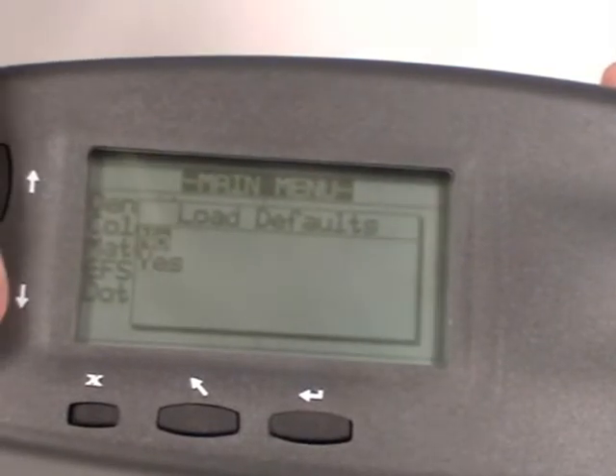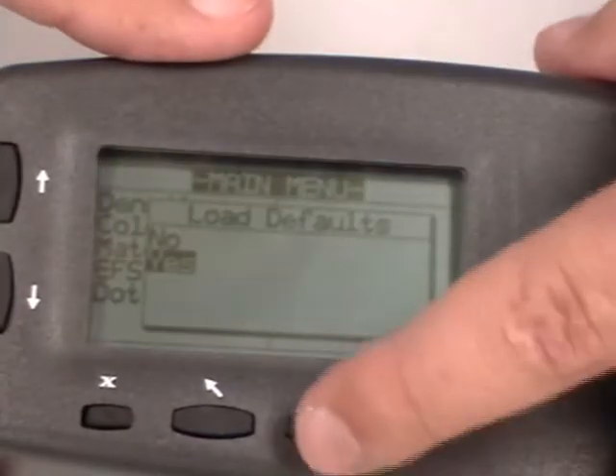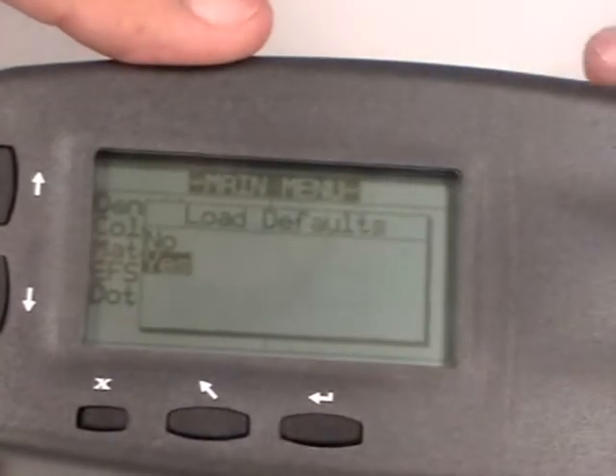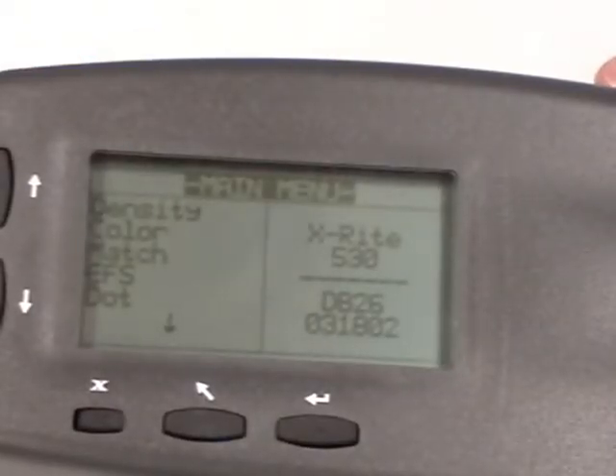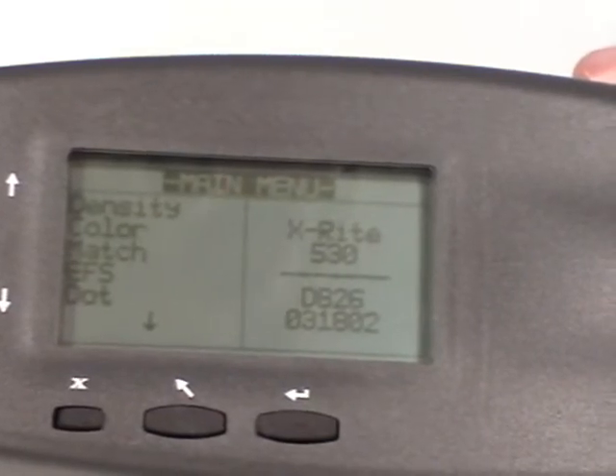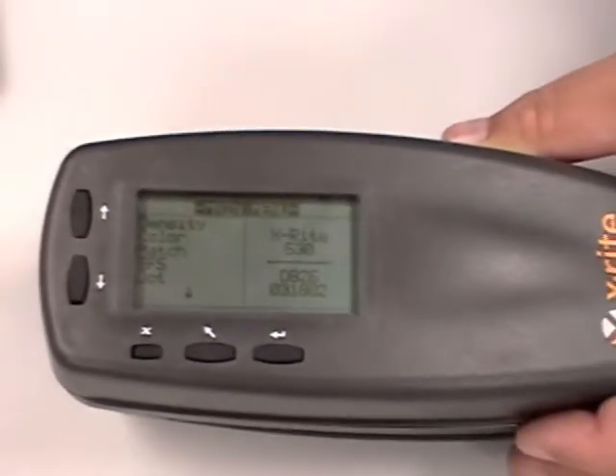You're going to press the up arrow, the down arrow, and the X all at the same time. The screen will flash, come back to 'Load Defaults', scroll down to highlight 'Yes', press the Enter key. The screen will flash off once again, come back — we've just reset the 530. Also remember, every time after a reset, you have to do a full calibration.